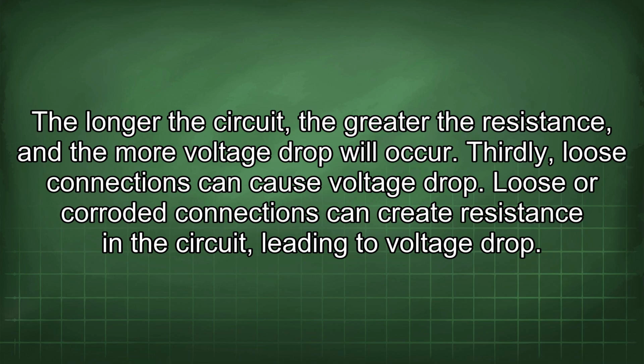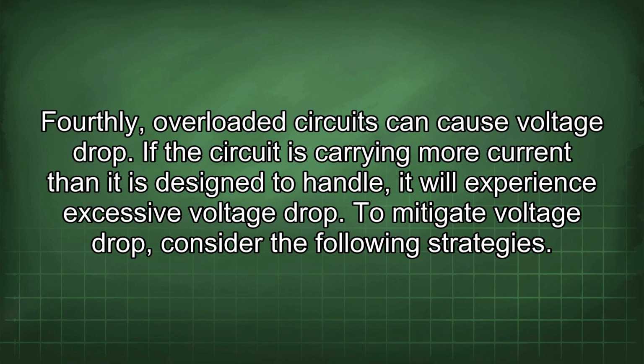Thirdly, loose connections can cause voltage drop. Loose or corroded connections can create resistance in the circuit, leading to voltage drop. Fourthly, overloaded circuits can cause voltage drop. If the circuit is carrying more current than it is designed to handle, it will experience excessive voltage drop.